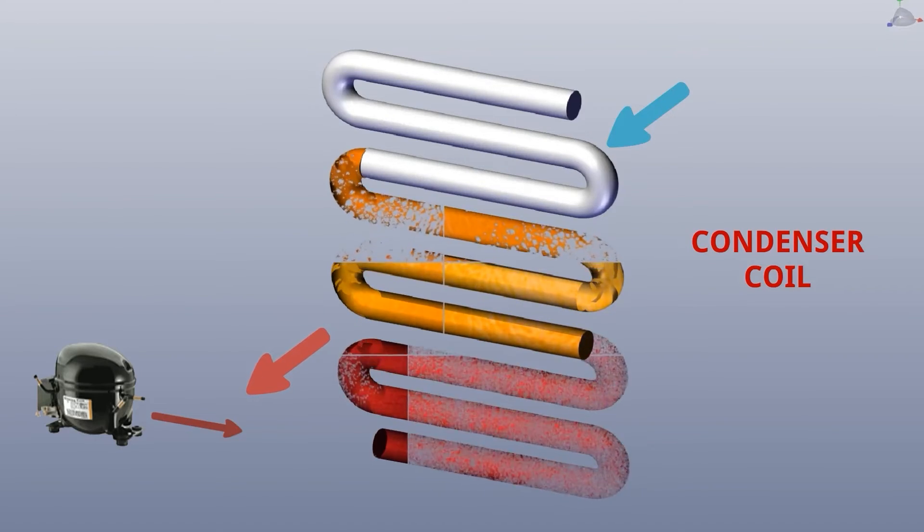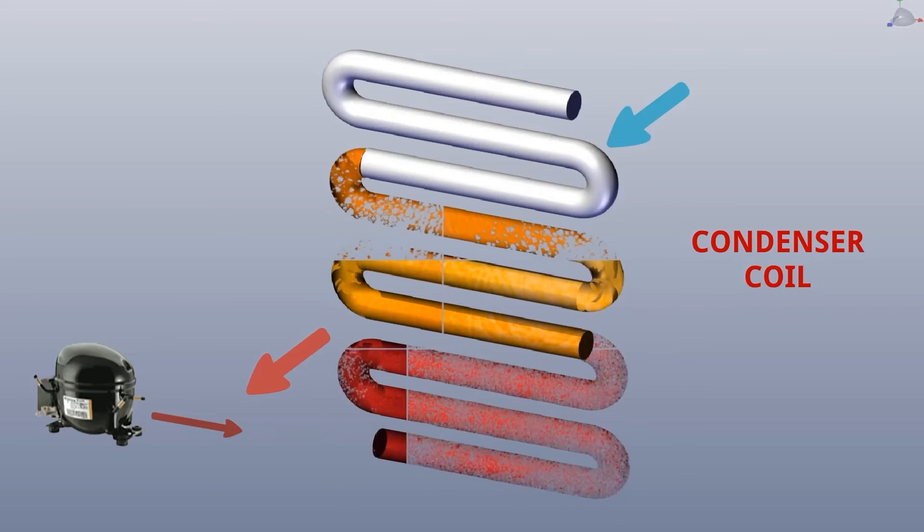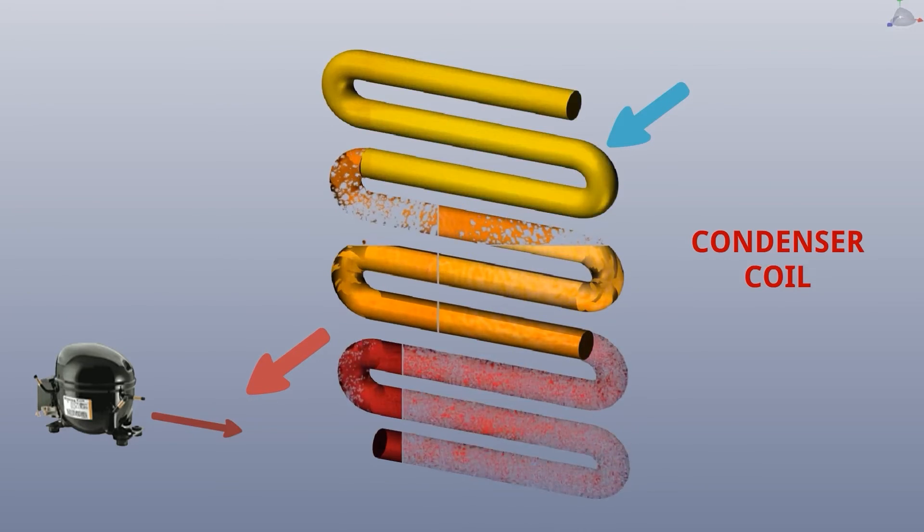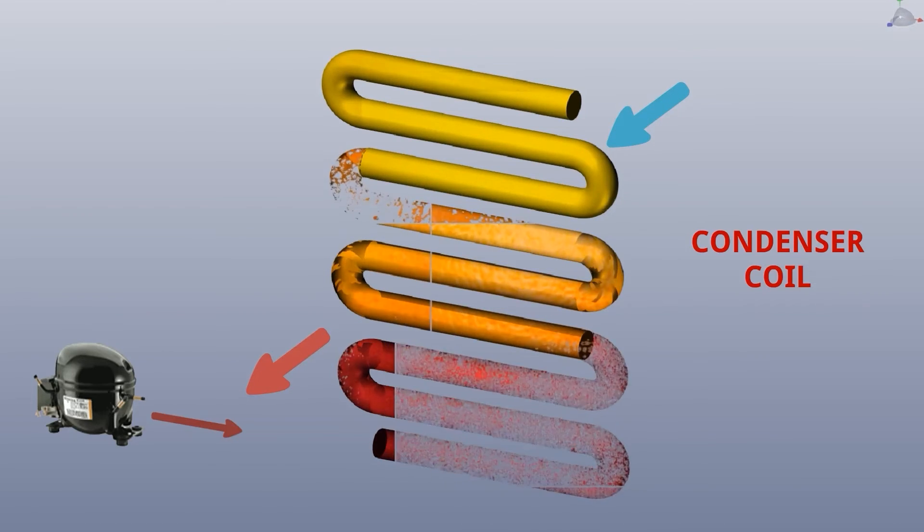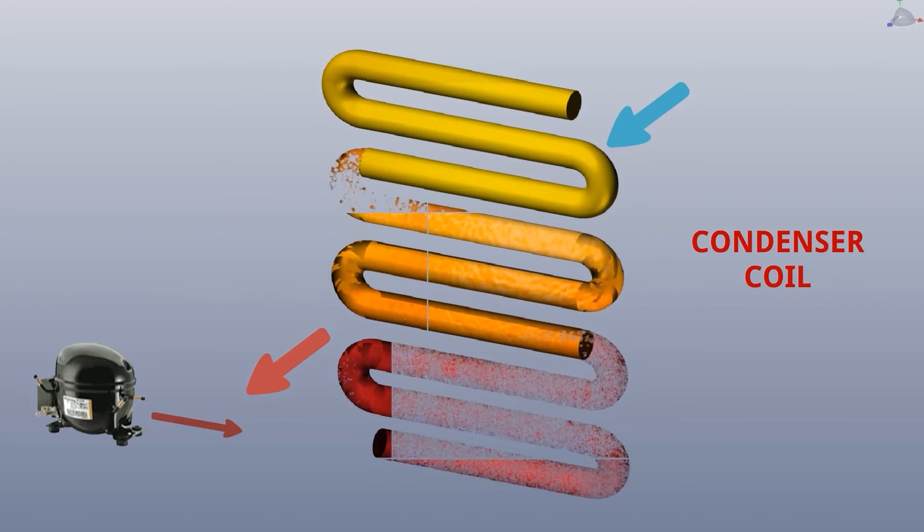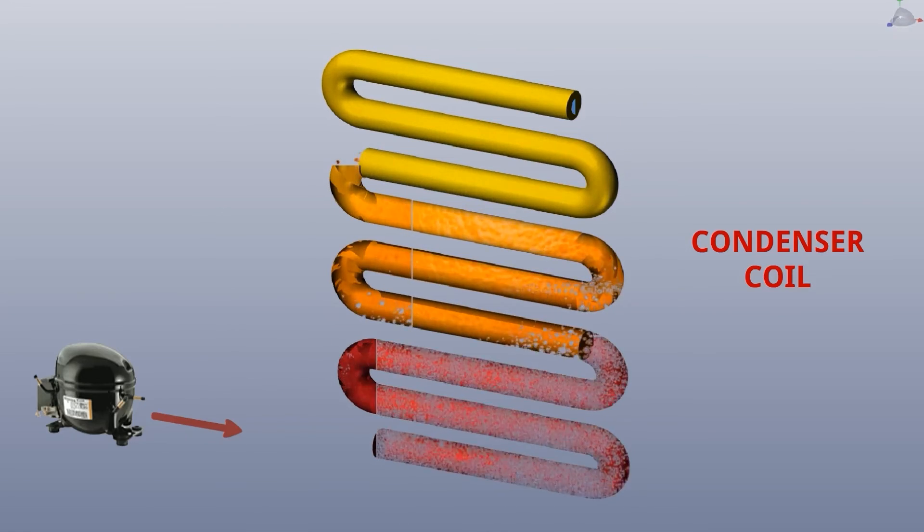The reduction of temperature makes the superheated refrigerant vapor into saturated vapor. Further reduction of heat changes the vapor into liquid. This is the liquid; however, it has a small amount of vapor as well at the outlet of the condenser coil.